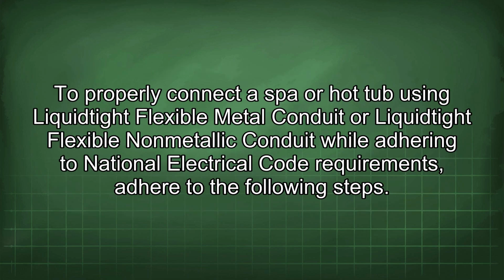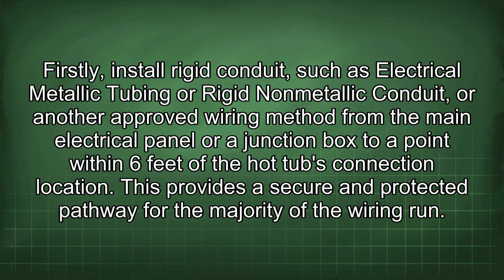To properly connect a spa or hot tub using liquid-tight flexible metal conduit or liquid-tight flexible non-metallic conduit while adhering to National Electrical Code requirements, follow these steps. Firstly, install rigid conduit such as electrical metallic tubing or rigid non-metallic conduit, or another approved wiring method, from the main electrical panel or a junction box to a point within 6 feet of the hot tub's connection location. This provides a secure and protected pathway for the majority of the wiring run.